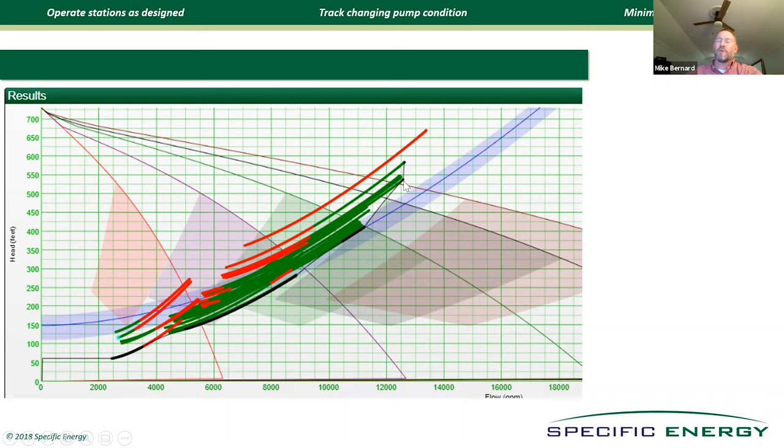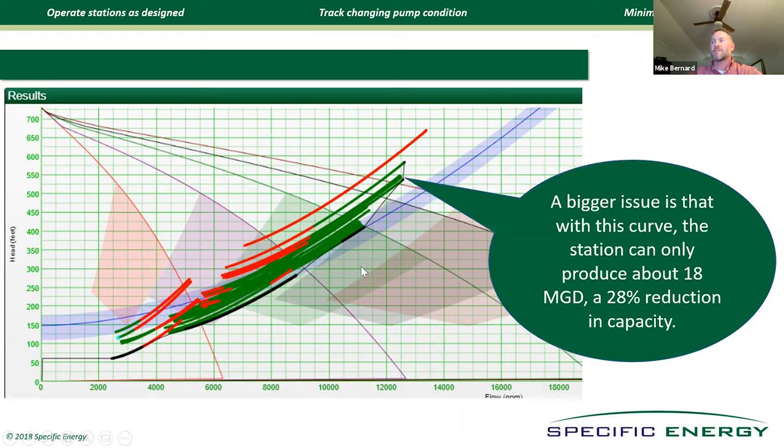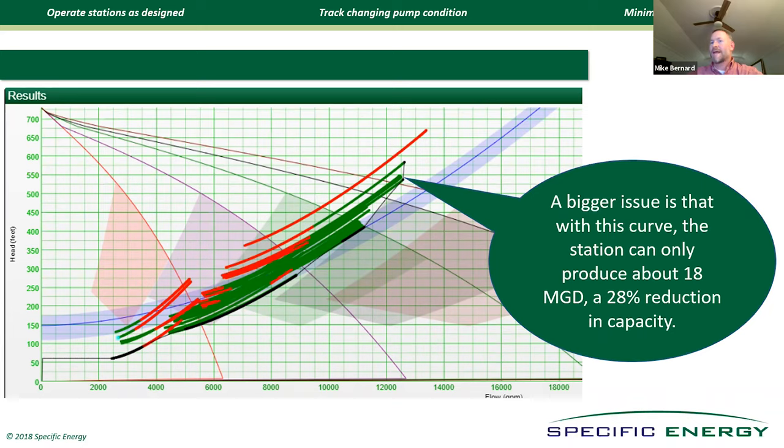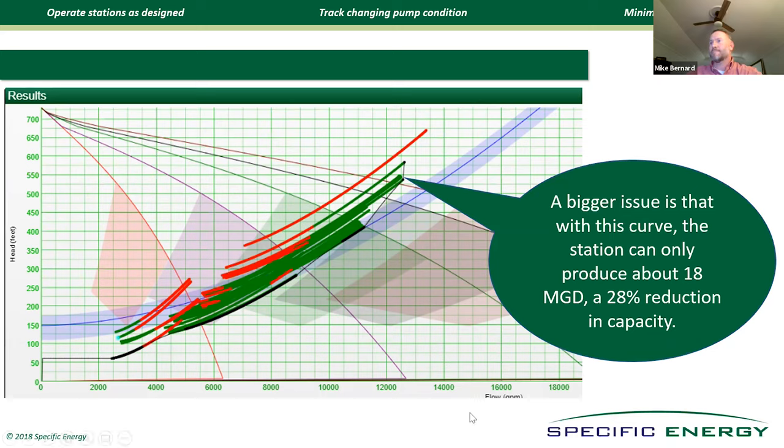A bigger deal for this particular pump station is the loss of capacity. One of the nice things in our system, if you come into the specific energy map and you just click on these dots that are associated with the four pump curves, it'll tell you in real time what your firm capacity is. And in this case, it's not 25 MGD. They've lost 28% of the capacity of this station. It's now an 18 MGD station. It was at this point that Casey went, oh my God, Mike, you're my new best friend. I need you to tell my managers this because I keep telling them that we can't get 25 MGD out of this station. And they just keep telling me, well, the engineer said it's a 25 MGD station. Well, it was. When it had new impellers and the line wasn't full of air, it could do that, but it can't now. It was almost a very big deal in the peak hot weather time this summer for them.